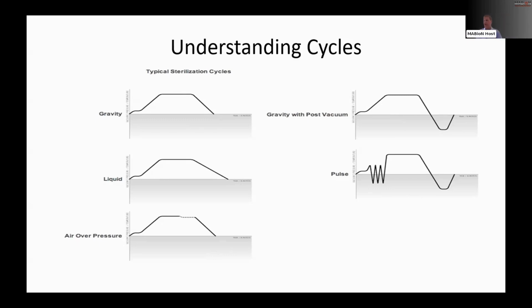And this is where the Bowie Dick comes into play. This is what they're looking for. You're looking for that deep penetration. And you can see just how quickly they go up and down. Literally, with these cycles, you should be reaching pressure and reaching vacuum within 45 seconds to a minute if your autoclave is actually correct. And it is a brutal, violent forcing in and pulling out, and it just drives that steam in deeper and deeper.